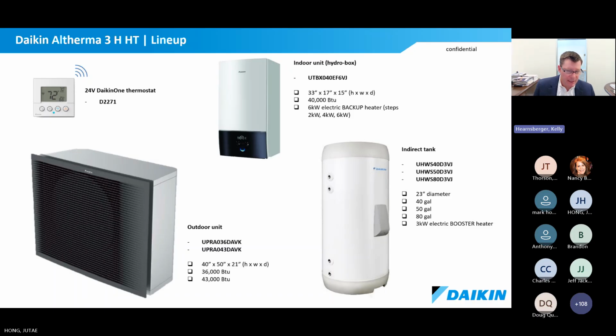But then you can see there are two unique sizes of the outdoor unit. And by the way, don't let those fool you: the 36,000 BTU and 43,000 BTU output units. There are definitely some sizing rules around this, but just to give you an idea, BTUs are BTUs at the end of the day, but you've got to think about this product as a room-by-room heating and cooling load design instead of a block load. And a lot of people don't understand that boilers are significantly oversized in northern markets, sometimes by a factor of two or three. So it's interesting to see what these systems can do.